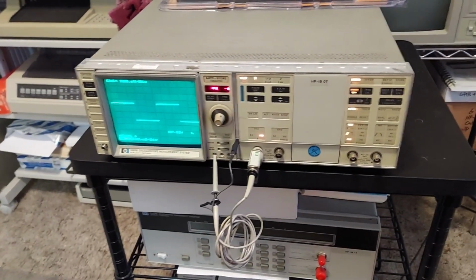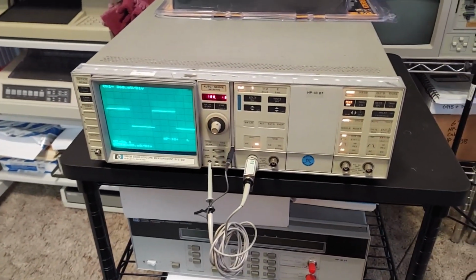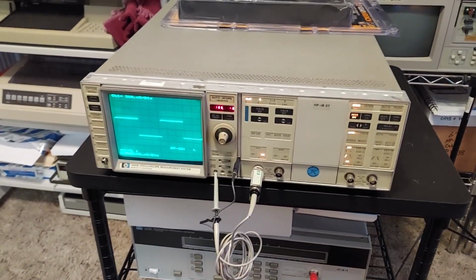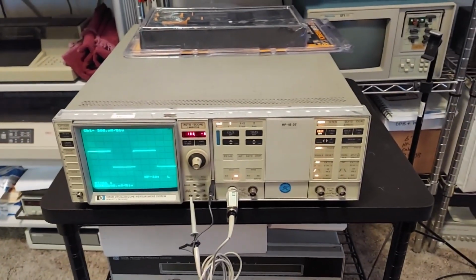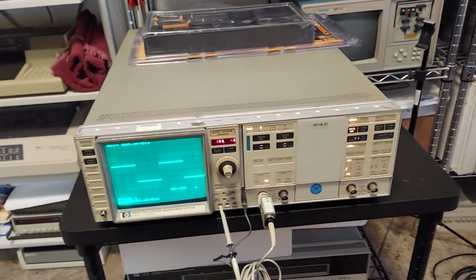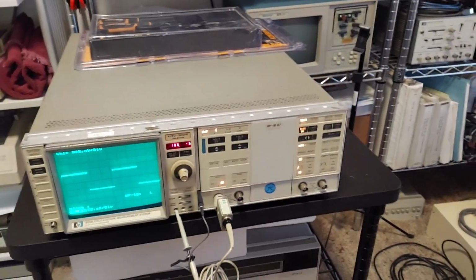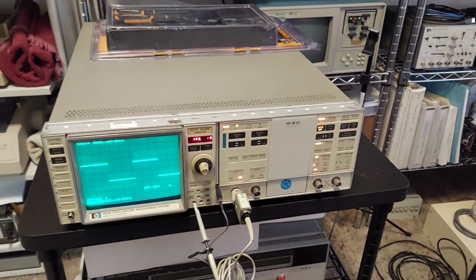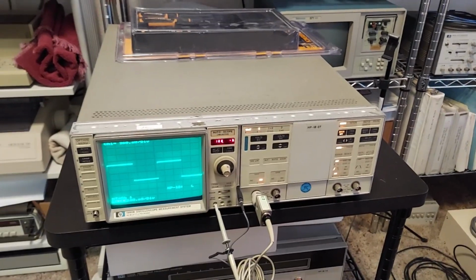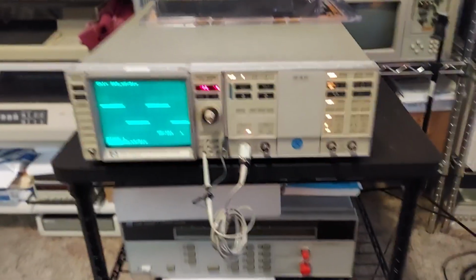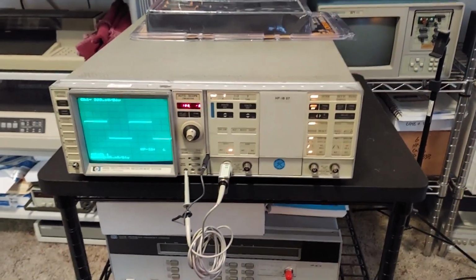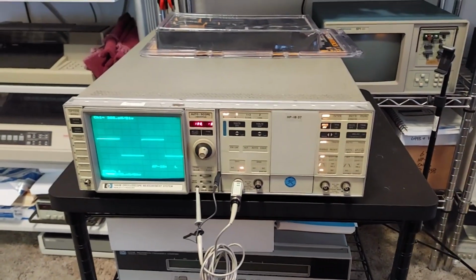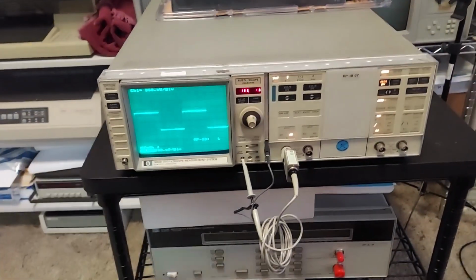Also, apparently, this thing has a backup battery in it. And it's been working so far, but it's located in the back of the unit. And when you disconnect that battery, it loses all of its calibration set points. So instead of messing with that, I think I'll just wait till it fails, and then I'll replace it, and then go through and recalibrate it again using the on-screen menus.